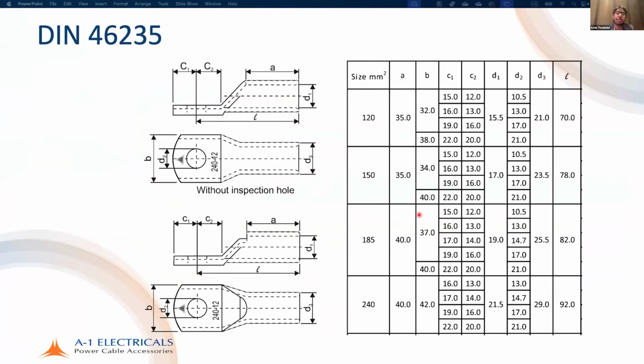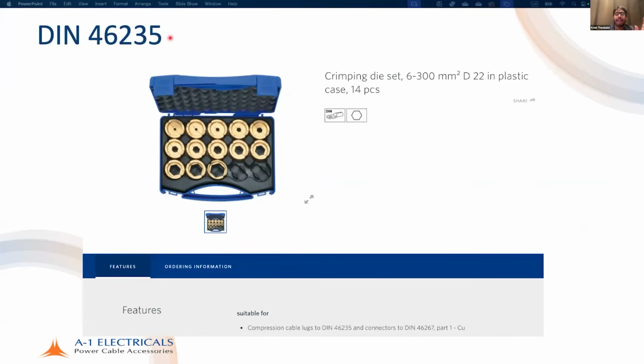The IEC standards provide for safety, for example, the test requirements for that particular product. But beyond that, for crimping and to ensure a good connection, using a DIN cable lug is the way to go, because then you have dimensional compatibility between the lug and the actual compression, the crimping tool, which is very, very, very important.